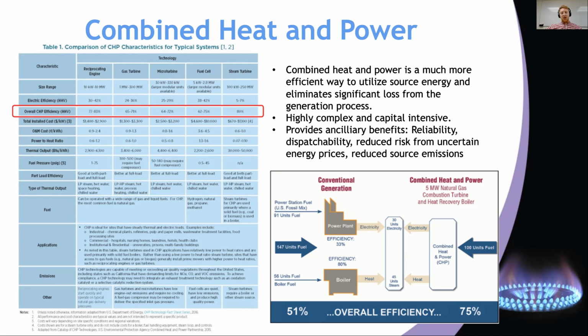And there are numerous resources to help calculate energy savings using metrics such as fuel chargeable to power and the fleet weighted average heat rate, which can help you convert between the electricity delivered and the gas used to generate that electricity. I have some information about that. I actually put together a pretty technical method of doing the energy savings analysis for this with Dominion's CHP incentive program, which is very limited and probably not something that most of our customers will be eligible for.